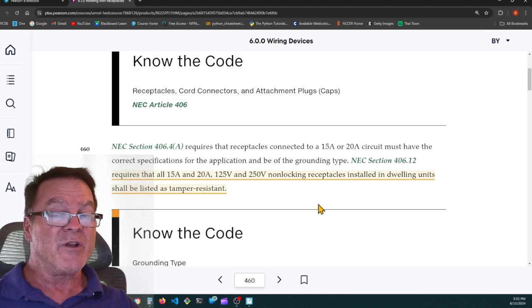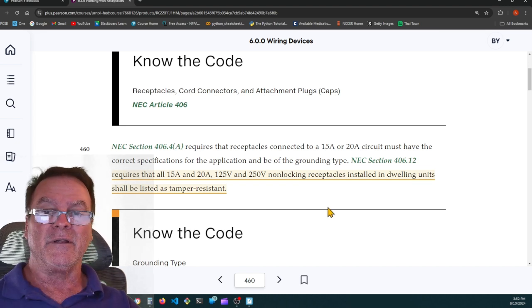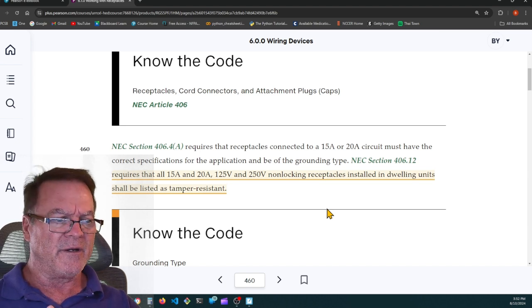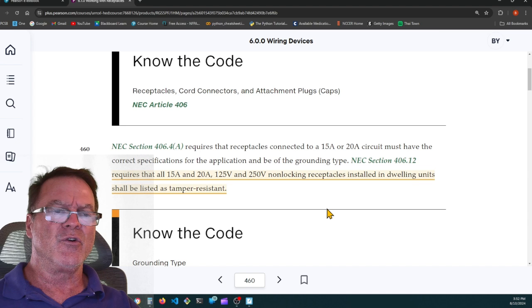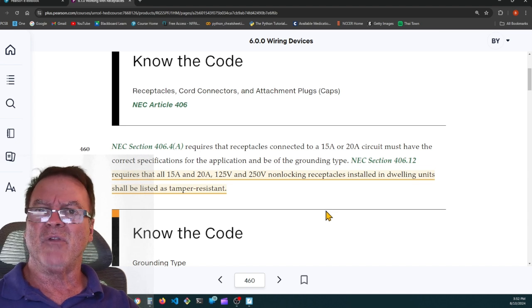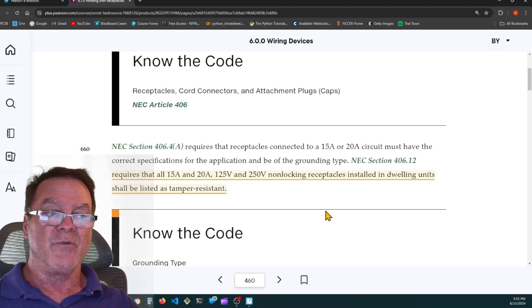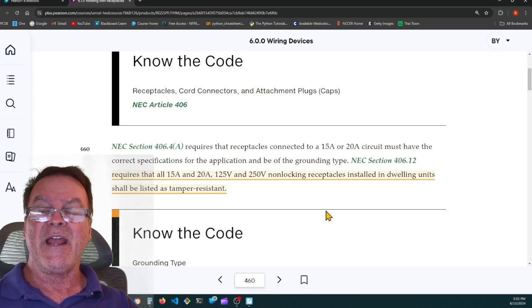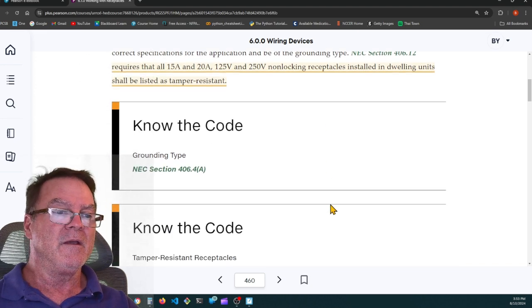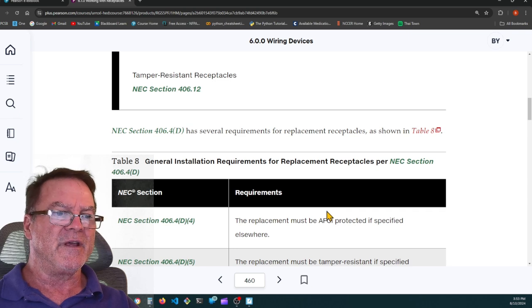Now, that's different when you have more than one outlet, when you have more than one receptacle. On branch circuits in the living room or small appliance branch circuits in the kitchen, you can put 15 amp receptacles on a 20 amp circuit. The receptacles themselves are rated at 15 amps, but you can have more than one of them and they can be on a 20 amp circuit. All right, we'll see if they mention that.